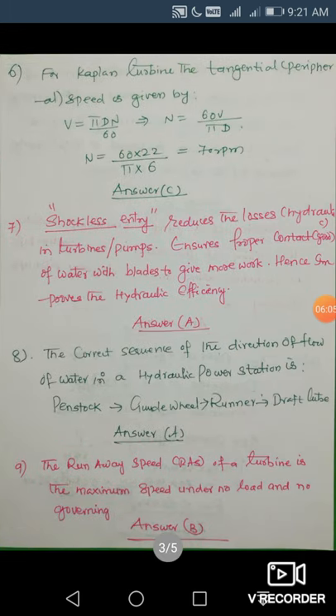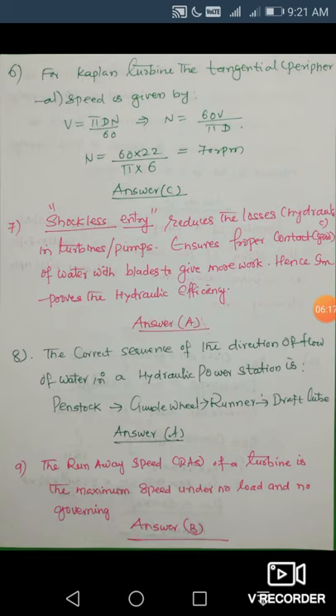Next question: in the Kaplan turbine, he has given the peripheral speed. The relationship between linear speed and diameter and RPM is v = πDN/60, so N = 60v/(πD). He has given v = 22 m/s and D = 6 m. Substituting: N = 60×22/(π×6) = 70 rpm. Kaplan turbines are axial flow reaction turbines with low speeds, typically around 70–80 rpm, not more than 120. The answer is C.